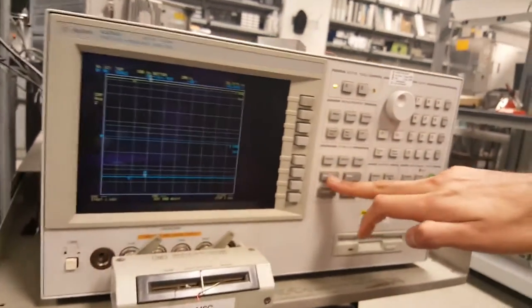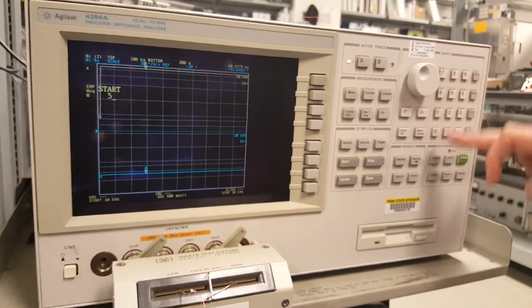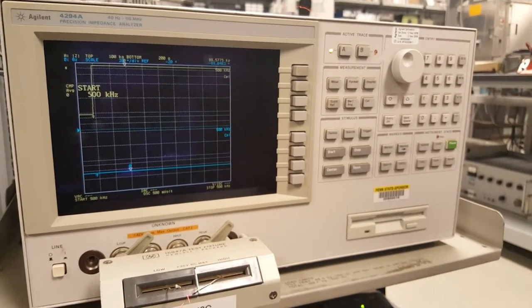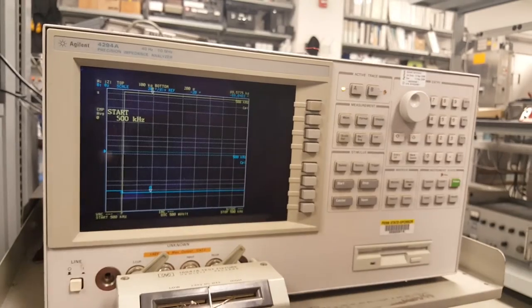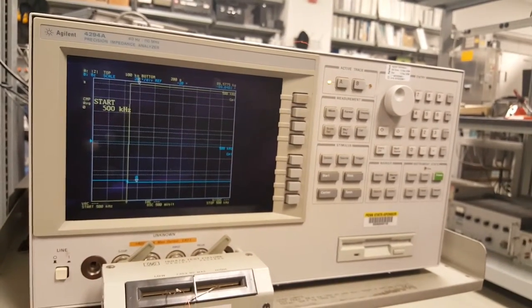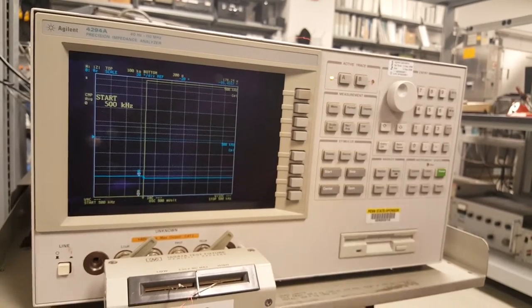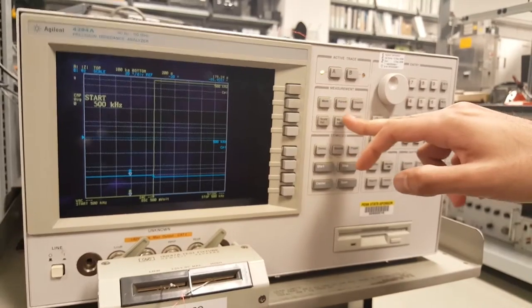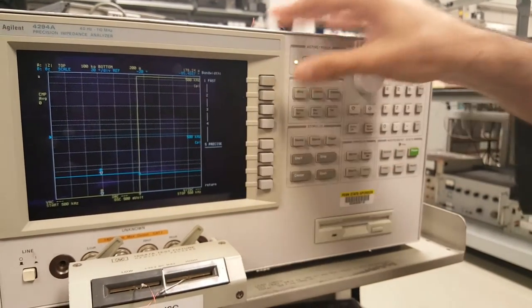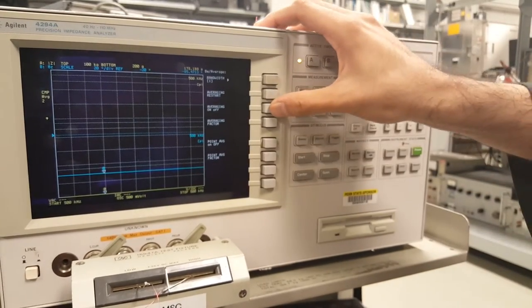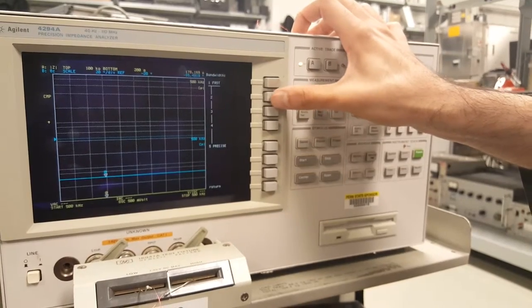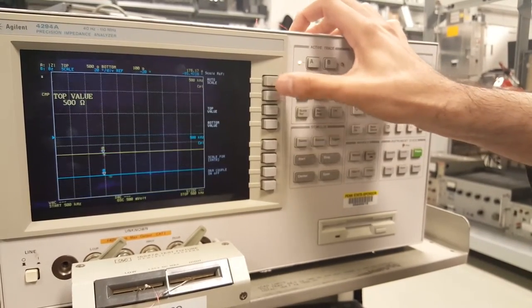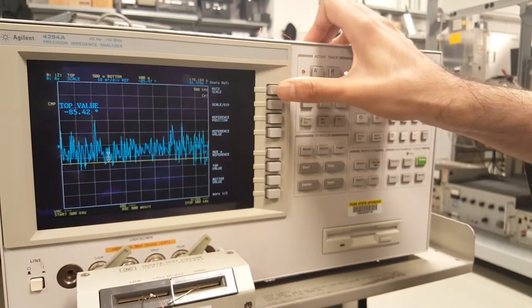But let's just do something. Let's start from 10 kHz. And let's go to 500 kHz. Because I want to show you something. We mentioned there's resonance going on like this. Resonance going on like that. Resonance going on like that. Depending on the frequency and the geometry. There's different resonance. So, I think we can change it off this. But when you're just playing with it. When you're just trying to get into the right frequency zone. You don't need to do this averaging. Or you don't need to, you can turn off averaging. Maybe bandwidth. You can totally put it on 2 or something. And then we can autoscale everything.